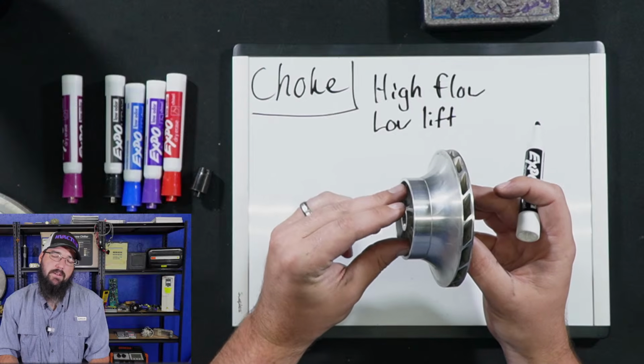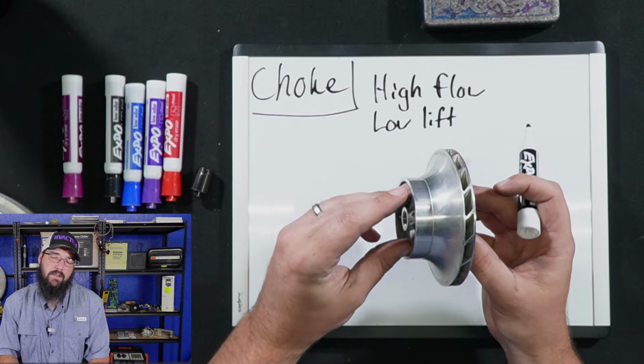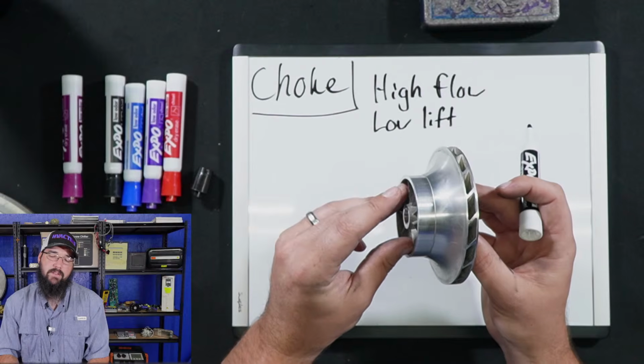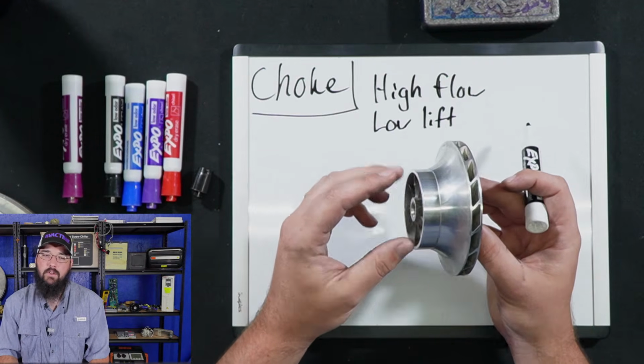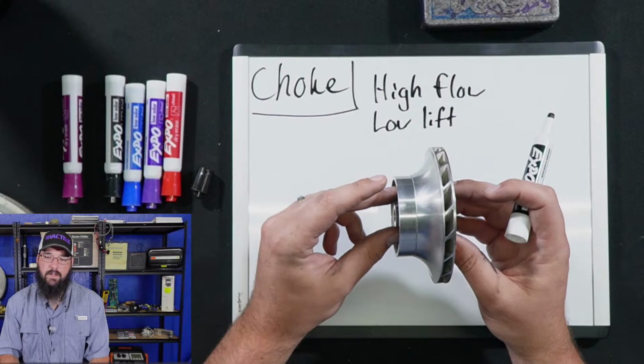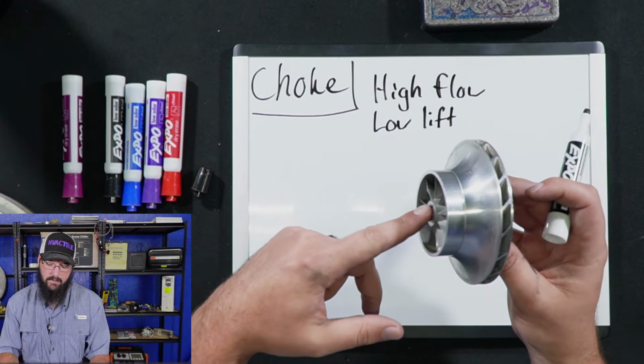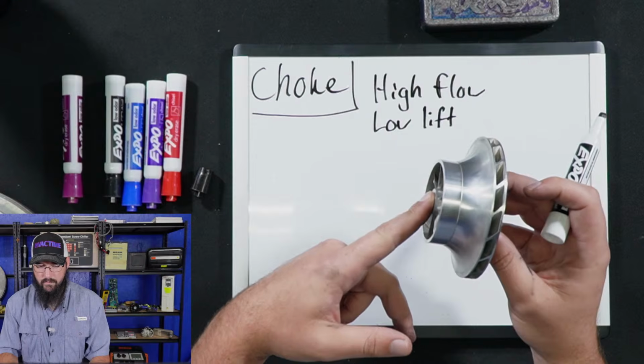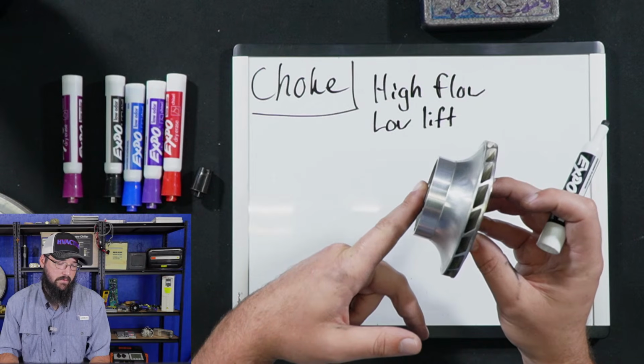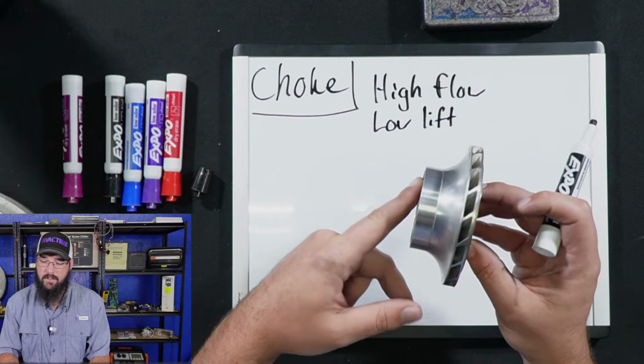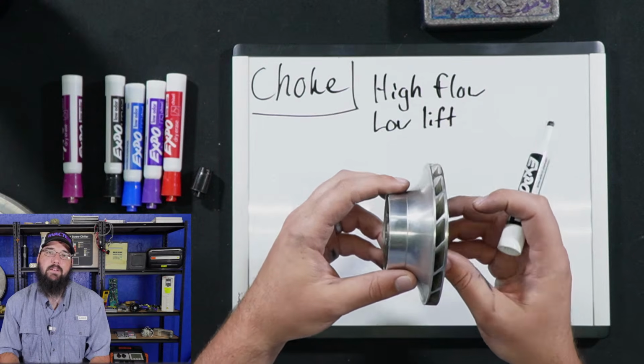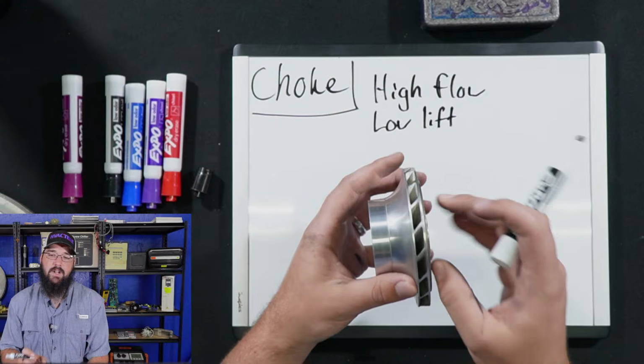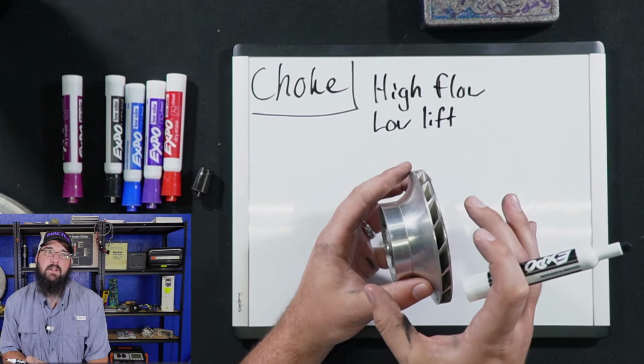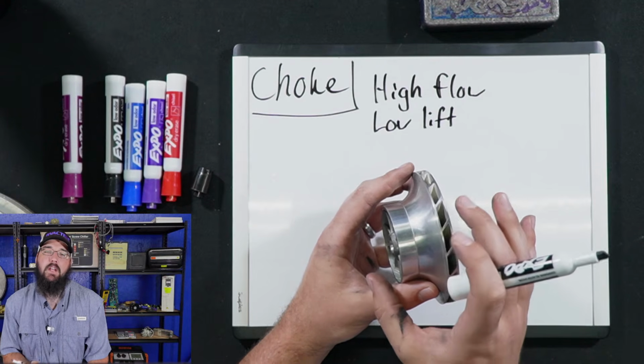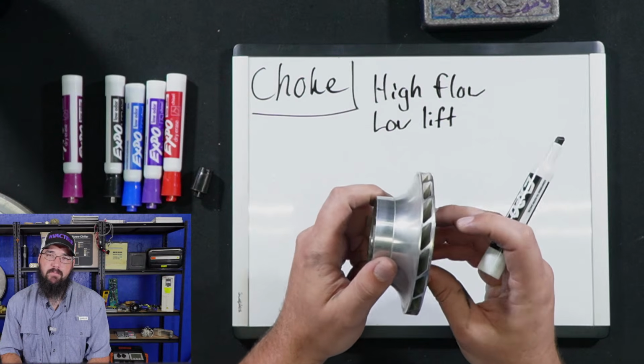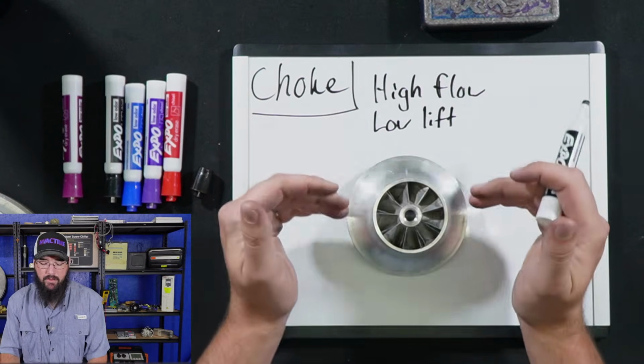And I'm trying to make sure I'm explaining this correctly. It's something we deal with less often, or at least that's been my experience. Usually we're dealing with a surge scenario, but in a choke situation, yeah, we could end up where we're just not able to maintain flow through the impeller because there's not enough lift to keep the impeller, call it, loaded. Hopefully that makes sense. That's when you're going to run into choke, though.